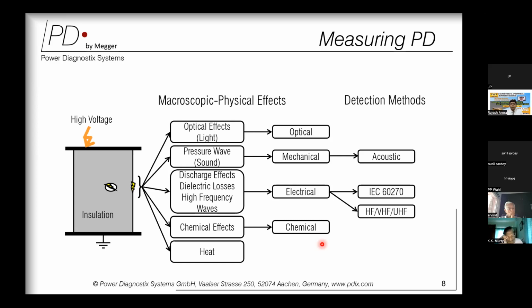If it is happening in one compartment, the light cannot be transmitted into another compartment, so the measurement is restricted if it is happening only in a particular compartment. So it's a limitation. We cannot use this method uniformly across measurement in GIS. Similarly, there are some limitations with respect to the chemical method, and hence we zero down that there are two usable methods which can be used for detection of partial discharge in GIS.